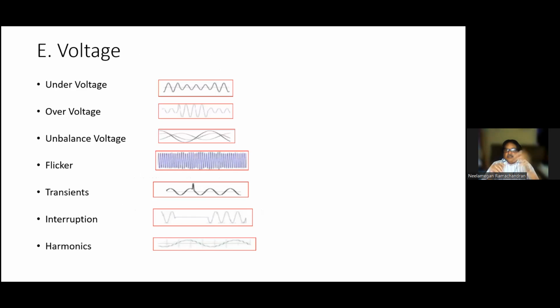And voltage, this many problems we have in voltage: under voltage, over voltage, unbalanced voltage, flicker, transients, interruptions, and of course harmonics. Over voltage, there was a problem because we had a dedicated feeder from the substation. A dedicated feeder was feeding one of the sections of the plant where we had this over voltage problem. During Sunday, we will be running only one section, which is still lagging in production. So they say only this section can work on Sunday. Rest all will be switched off. On that Sunday, we invariably face this problem.